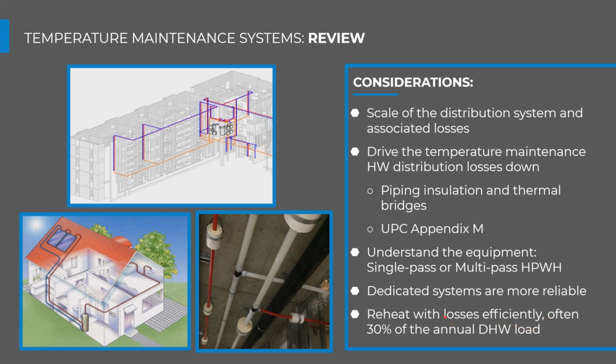And the last point here is we really want to reheat these losses efficiently, because they're losses. This is wasted energy, and it's 10% of the annual building load, or 30% of the annual domestic hot water load. So it's a significant portion of the amount of energy going into these buildings, and it's a loss. So we want to eliminate that loss whenever possible.